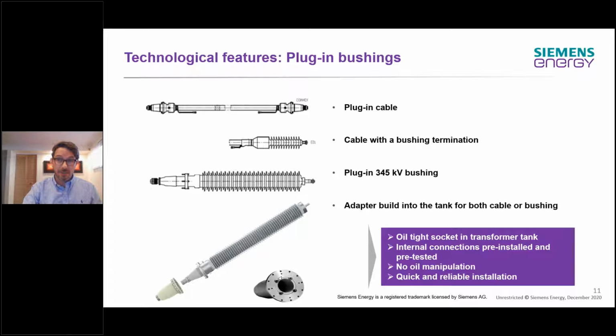And cable connections have been available for a long time. So we said, let's use that, but let's evaluate all options and possible uses around it. At the top of the slide, you see a conventional cable with 2 plug-in connections at both ends. But that same cable can have a bushing termination on one of the ends instead of the plug. And then we said, why not use that high voltage plug and attach it directly to the bottom end of a capacitive bushing? And so a plug-in high voltage bushing was born.